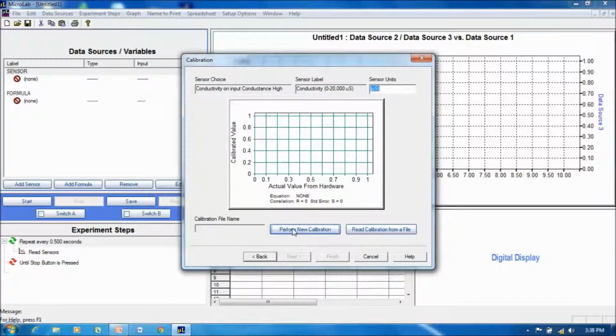We're going to perform a new calibration, and again for this calibration I've got 4 commercial standards ranging from 45 microsiemens per centimeter to 4,500 microsiemens per centimeter. For precise work, it's much better to have a smaller range with more samples over that smaller range, using just the range that you expect from your particular unknown solutions. The other thing to notice is the sensor units. We're going to use not microsiemens but microsiemens per centimeter. So let's perform that calibration.